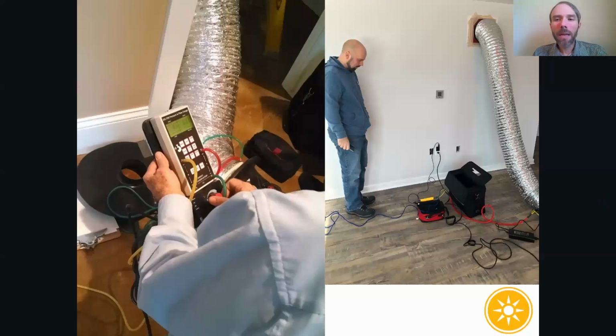If the ductwork can be confirmed as not panned in the joist and the sizing works well, then the second problem will be duct leakiness. The ducts will need to be tested by a qualified energy professional or rater to determine duct leakage in compliance with Energy Star duct leakage targets. Usually this test is also done in conjunction with that blower door test we talked about to get something called total duct leakage to the outside.